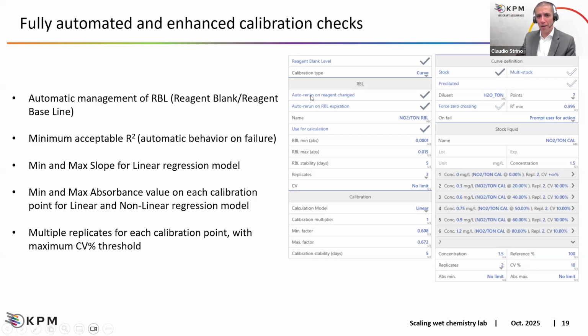And automatically, when the in-use bottle finishes and the instrument needs to swap to the new one, the instrument will automatically schedule and run the RBL. Also, RBL expiration: because the RBL, the baseline, is related to the stability of the reagent, meaning how often the reagent changes color over time, we can define the stability and ask the system, at the end of the stability, to automatically rerun. So everything is automated. And we can also check the minimum and maximum value and define when the color of our reagent is still acceptable to consider it a working reagent.